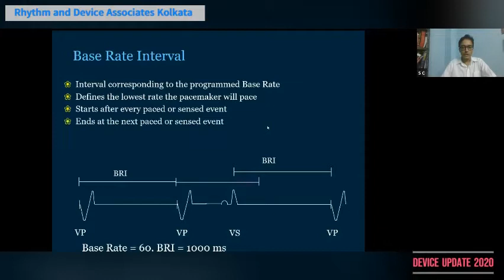So it is the interval corresponding to the programmed base rate. Mostly it is 60, sometimes we keep it at 70, and rarely at 50. This is the lowest rate at which the pacemaker will pace, and it starts after every paced or sensed event. Every word is important here. The base rate interval is triggered by either a paced event or a sensed event, whichever comes earlier in the timing cycle, and it ends with the next paced or sensed event. That is another important thing.